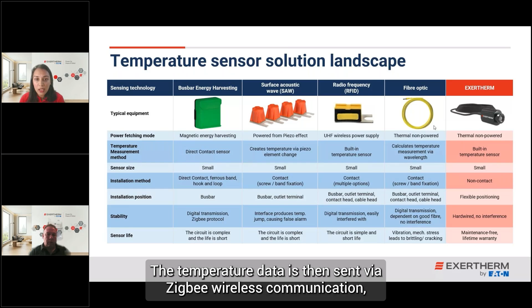Moving on, let's look at the different technologies and how they work. First, the busbar energy harvesting sensor. This is a small sensor, self-powered by the magnetic field of the powered circuit. It is secured to the connection with a loop and is in direct contact with the measured point. The temperature data is sent via Zigbee wireless communication, an open source protocol, to mobile phones and other devices. The sensor itself is wireless and battery-free.